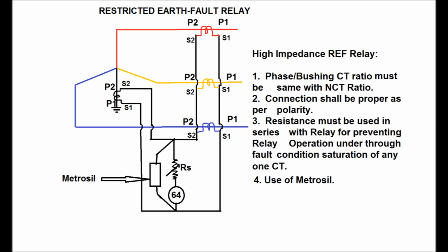Number 3 is that a resistance must be used in series with the relay for preventing relay operation under through fault condition, considering one of the CTs is under saturated condition.